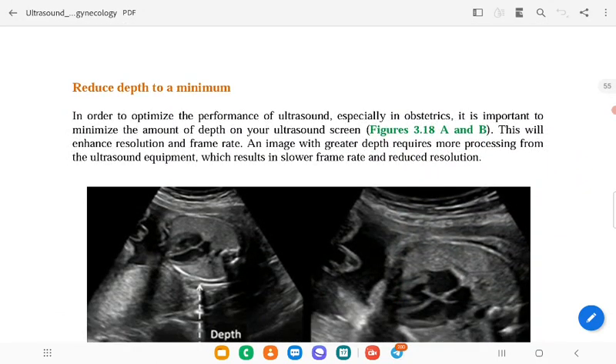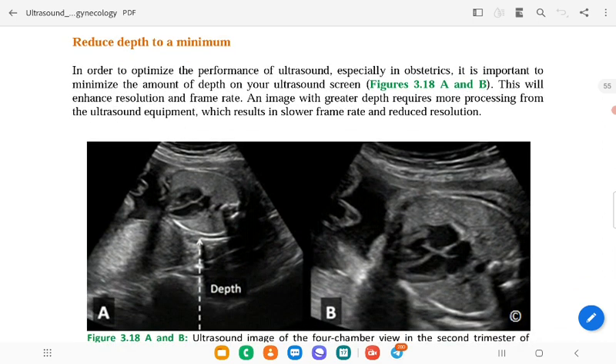Reduce depth to minimum in order to optimize the performance of ultrasound. Especially in obstetrics, it is important to minimize the depth on your ultrasound screen. This will enhance resolution and frame rate. An image with greater depth requires more processing from the ultrasound equipment, which results in lower frame rate and reduced resolution.